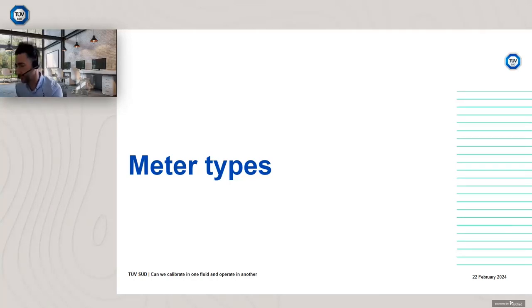So that's a bit about the background. So as you can see, there certainly is a requirement for calibrating in one fluid and operating in another due to the lack of traceable flow facilities offering these challenging fluids. There's also folk that simply want to calibrate in water because it's cheap, readily available, and simply easier than calibrating in, say, gas or calibrating in a high viscosity fluid. So we can also understand those drivers as well.